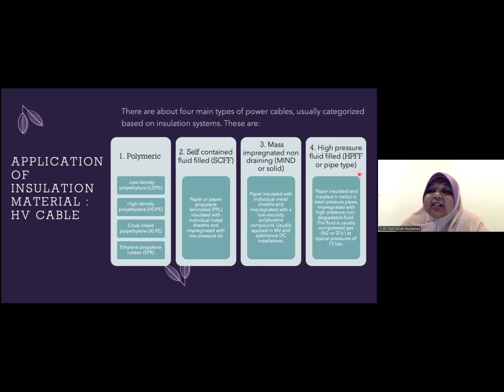Then we have the last type, which is high pressure filled cable, HPFF cable, or we call it pipe type cable. So these are cables that are put in a pipe. Paper insulated and installed in a trefoil in a steel pressure pipe, impregnated with a high pressure non-degradable fluid. The fluid is usually composed of gas, SF6 or nitrogen, at a specific pressure, normally 15 bar.